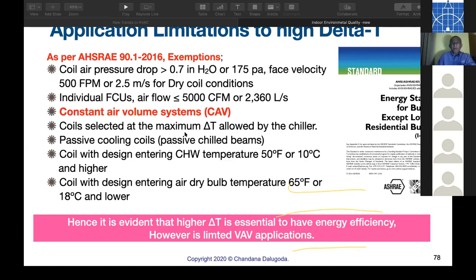Coil selected at the maximum delta T allowed by the chiller. If the chiller is not allowing, you can't do that. Passive cooling coils, chilled beams, out. No, you can't have high delta T. Coil with design entering chilled water temperatures of 10 or higher, you can't have high delta T because we have to operate at 5. Coil with design entering air dry bulb temperatures of 18°C and lower. So those are the exemptions. With exemptions, this is quite good. But you've got to remember, these are the limitations.